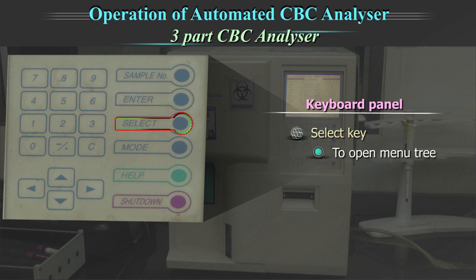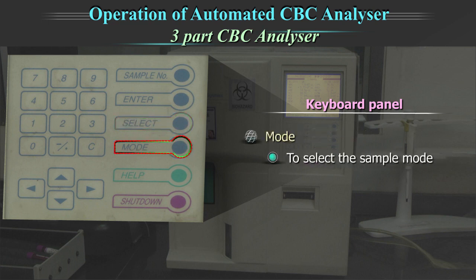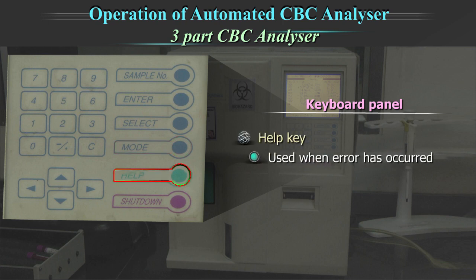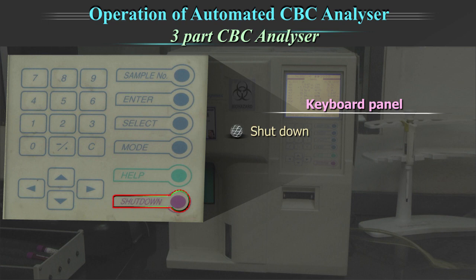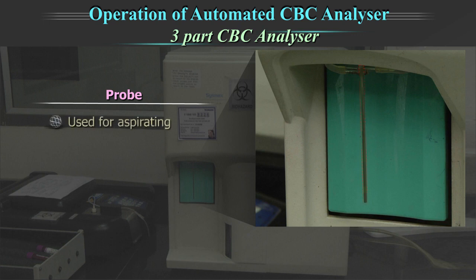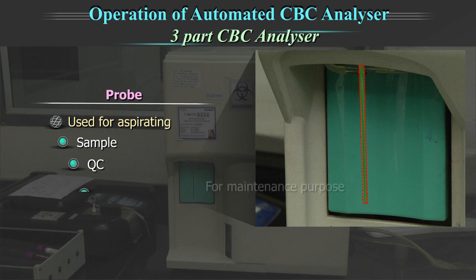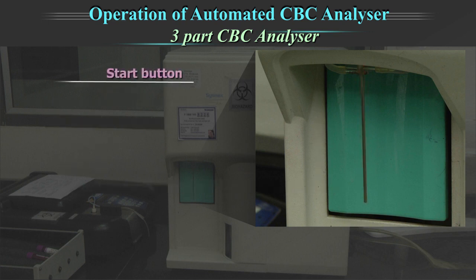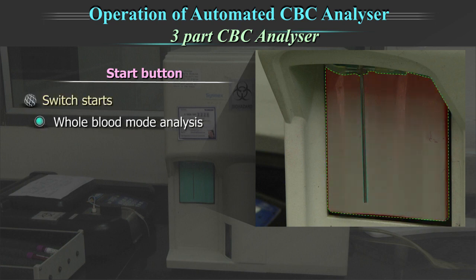Select key helps you to open the menu tree for further options. Mode helps to select the sample mode, which could be the whole blood mode or the pre-dilution mode. Help key is used when an error has occurred. Shutdown is used to shut down the machine. Probe. Probe is used for aspirating the sample, the quality control material, or for maintenance purposes. The Start button. This switch starts the whole blood mode analysis and the pre-diluted mode analysis.